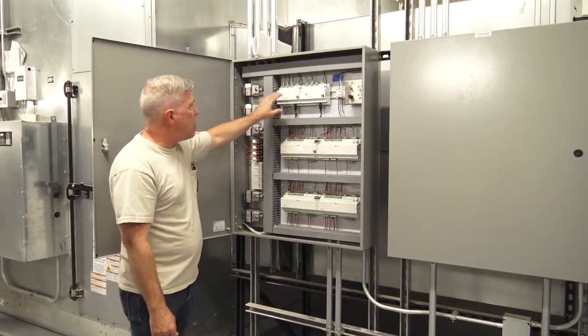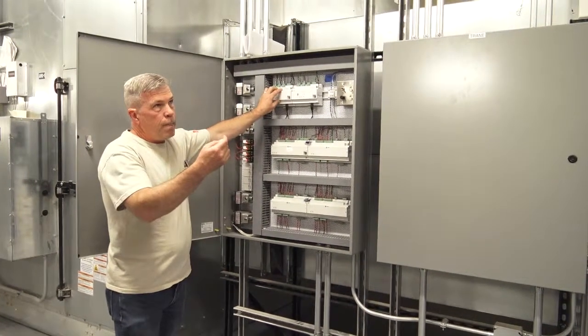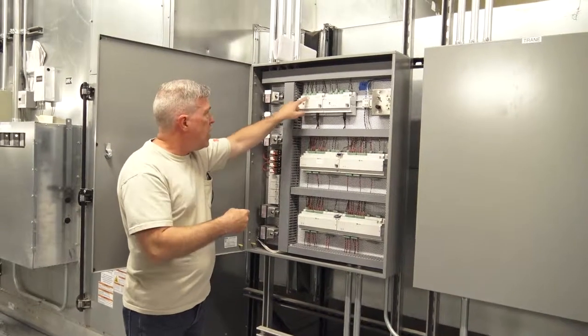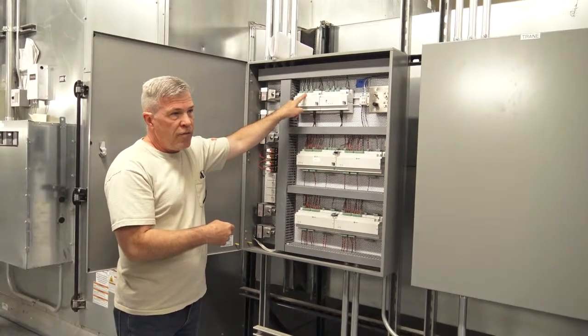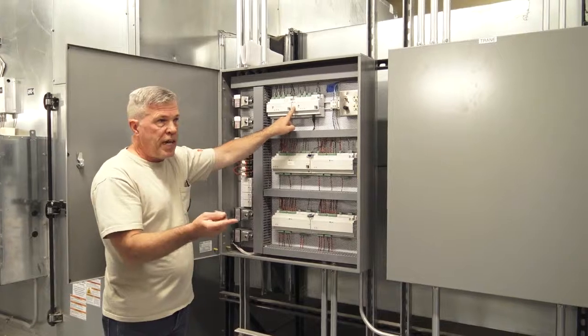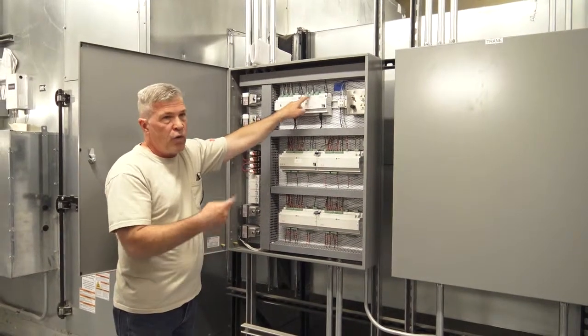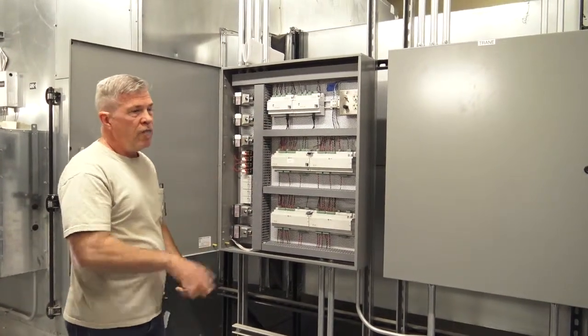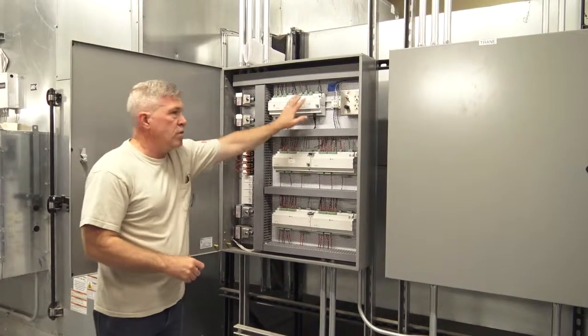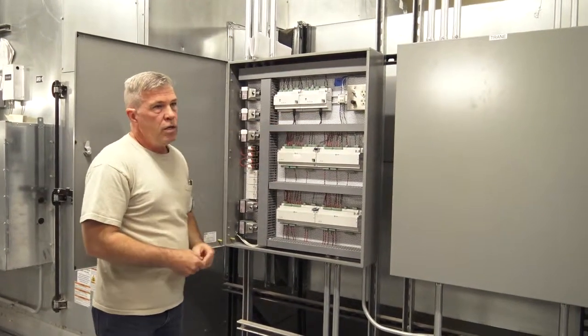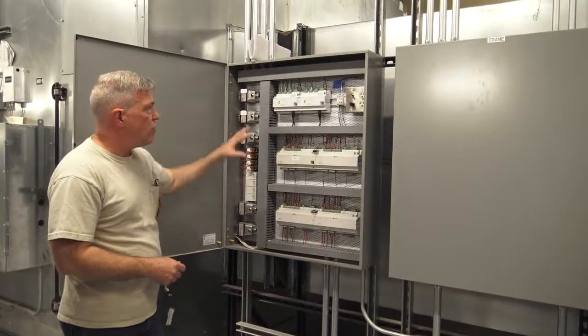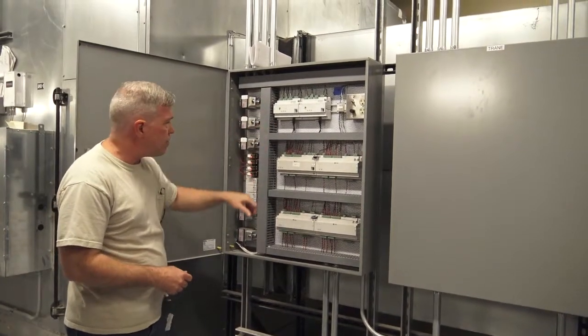This one does the east side of the building, link 1 is first floor, link 2 is second floor. This one does the west side, link 1 first floor, link 2 second floor. So if the west side second floor is down, this is where to look. That's the quickest way to check communication within the building.